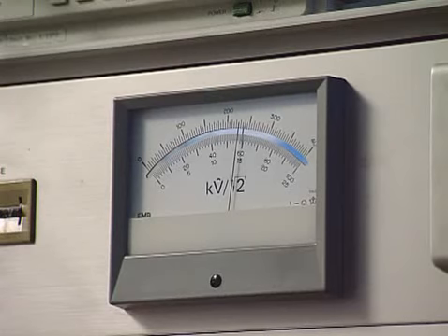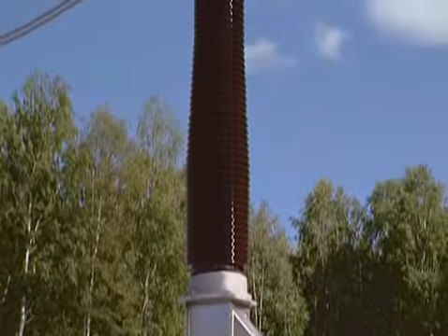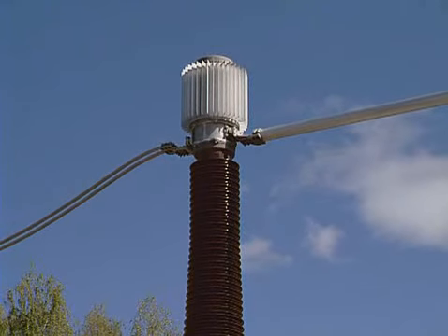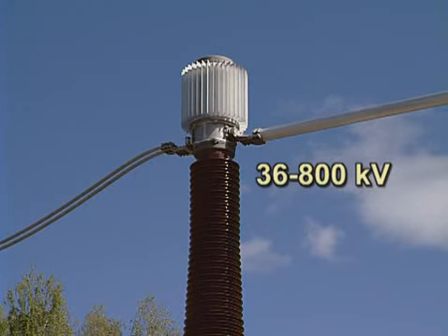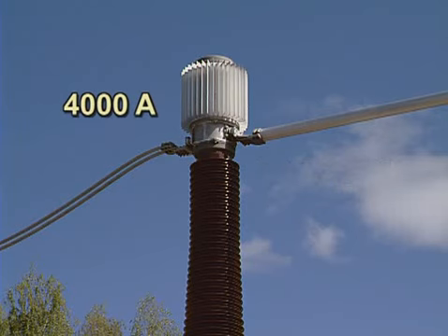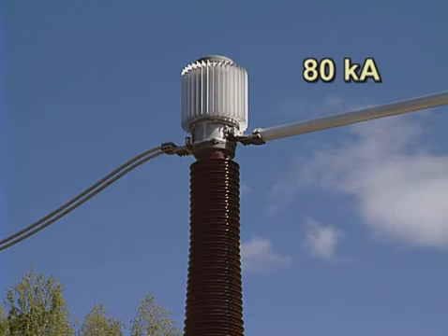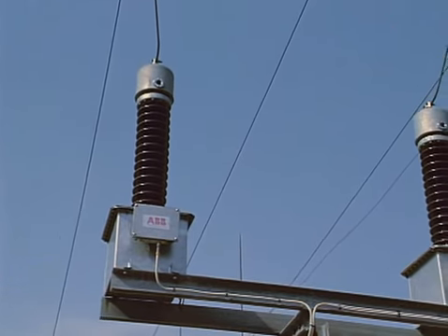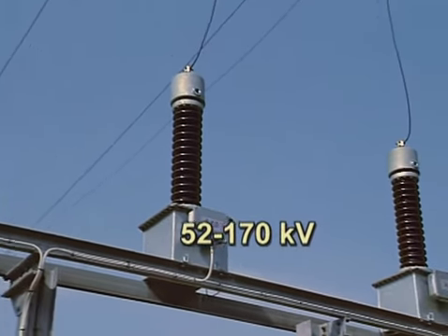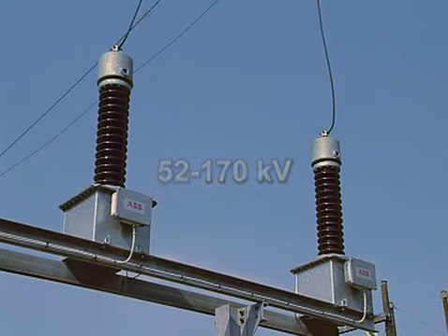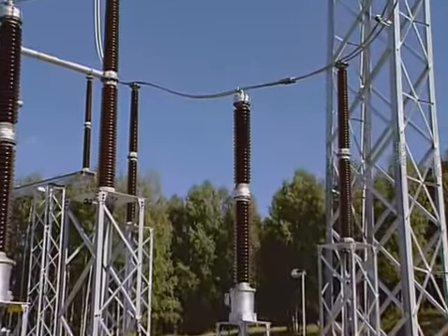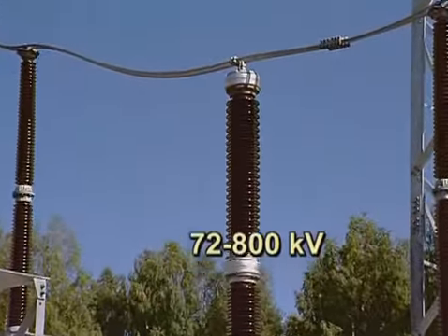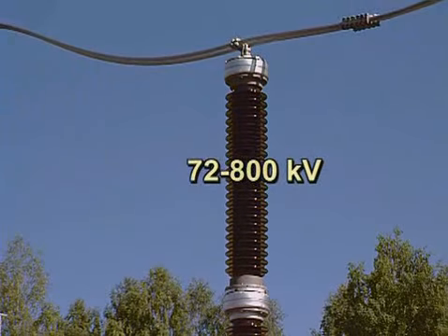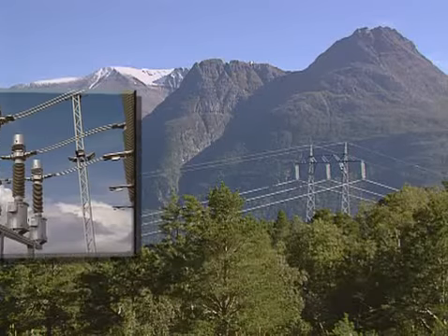ABB's complete range of instrument transformers consists of IMB current transformers available in voltages from 36 to 800 kilovolts with current up to 4,000 amperes and short circuit current up to 80 kiloamperes. The EMF inductive voltage transformer is available for voltages from 52 to 170 kilovolts. And the CP capacitive voltage transformer is available for voltages from 72 to 800 kilovolts. All of the instrument transformers are custom-made to meet the customer's requirements.